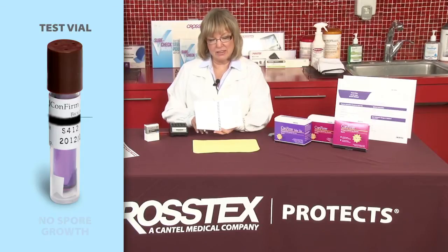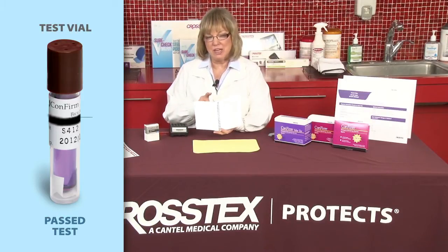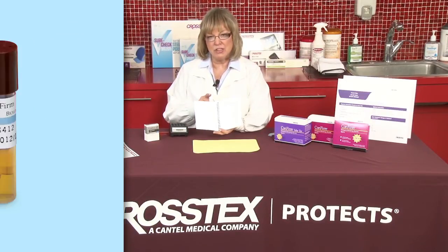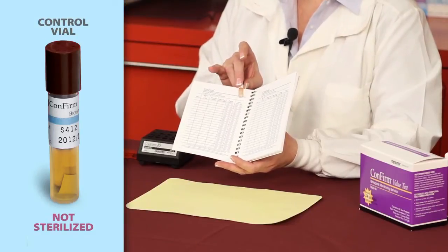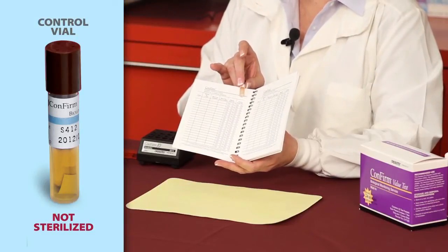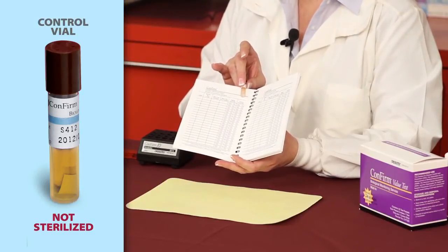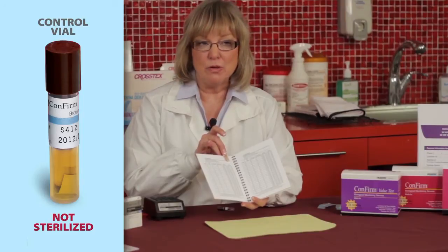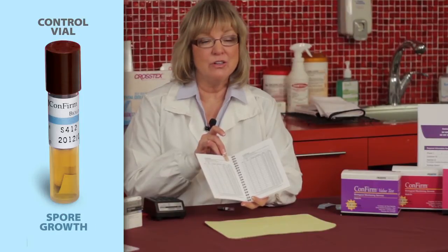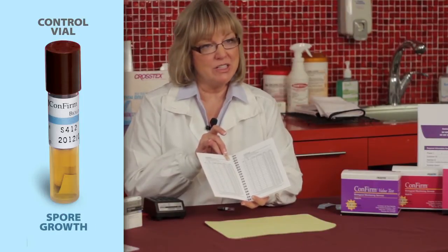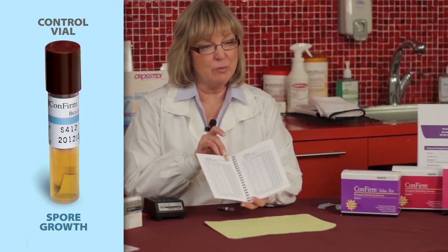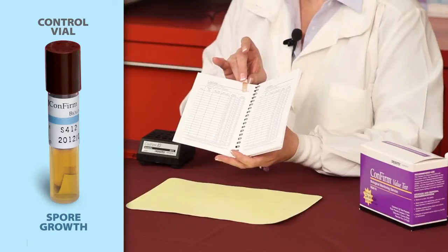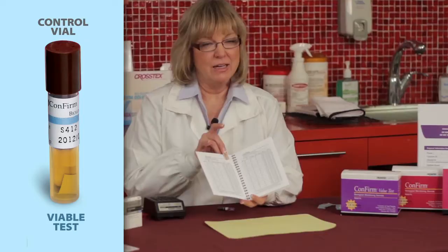We would then look at the control vial, which, remember, was not processed through the sterilizer. When it comes out of the incubator and we see that it has changed colors, that indicates that spore growth has occurred, which means the test was viable, and it means that the control, in fact, passed.